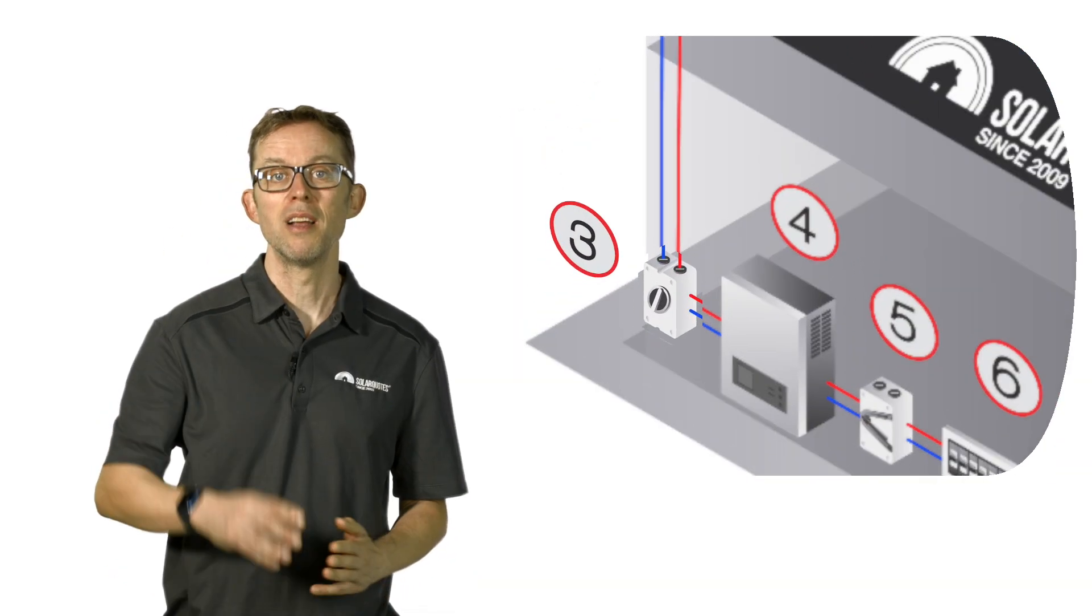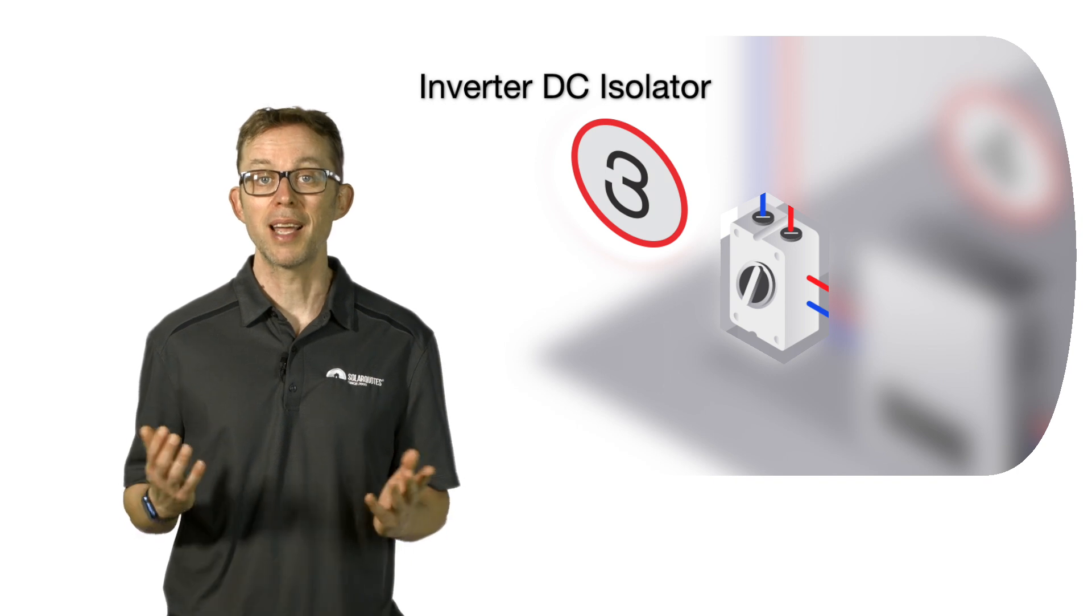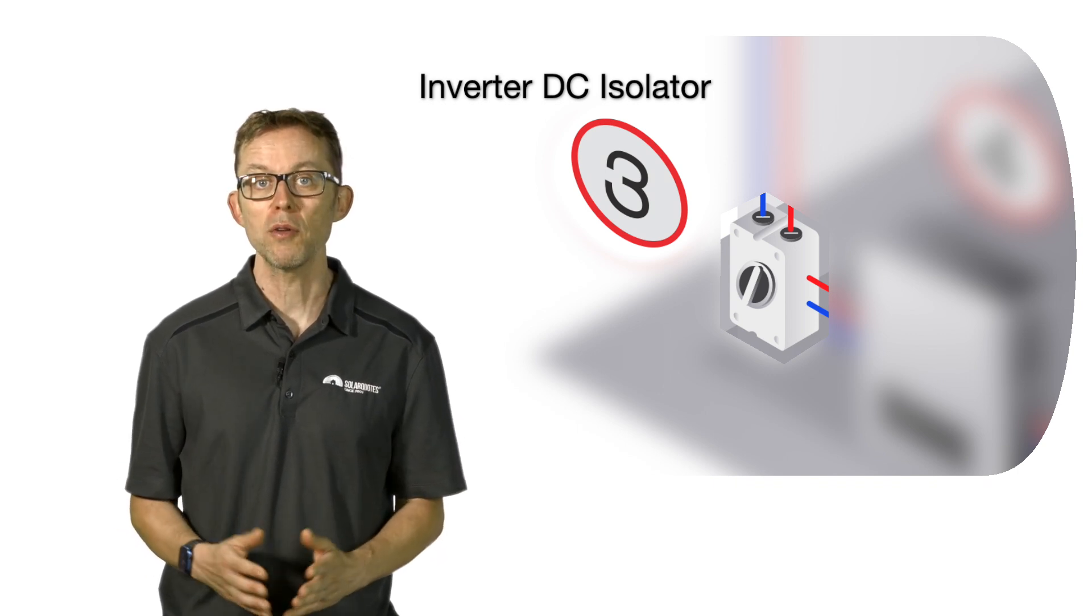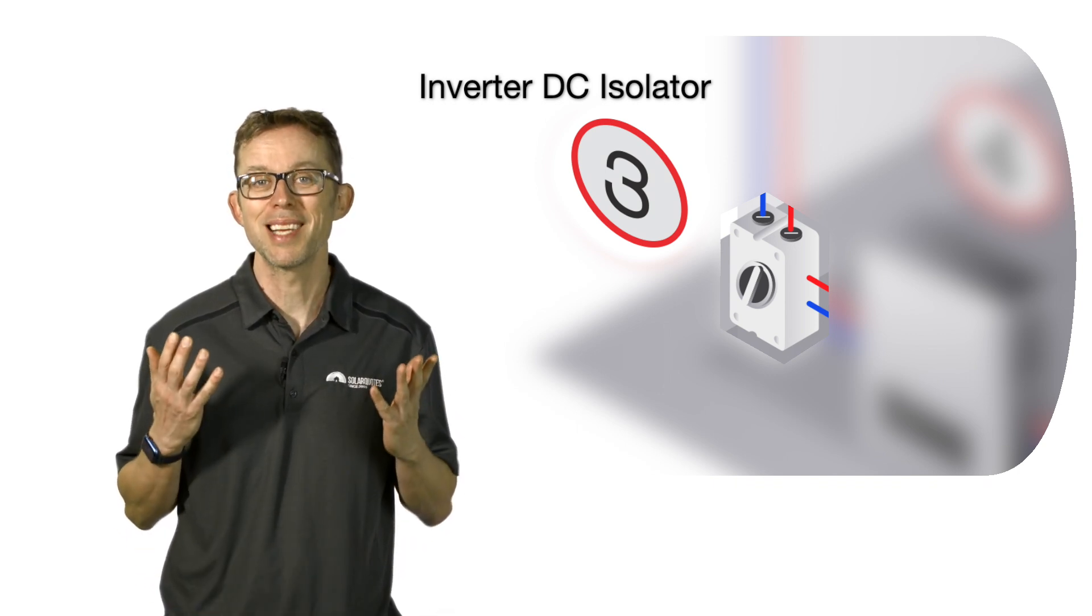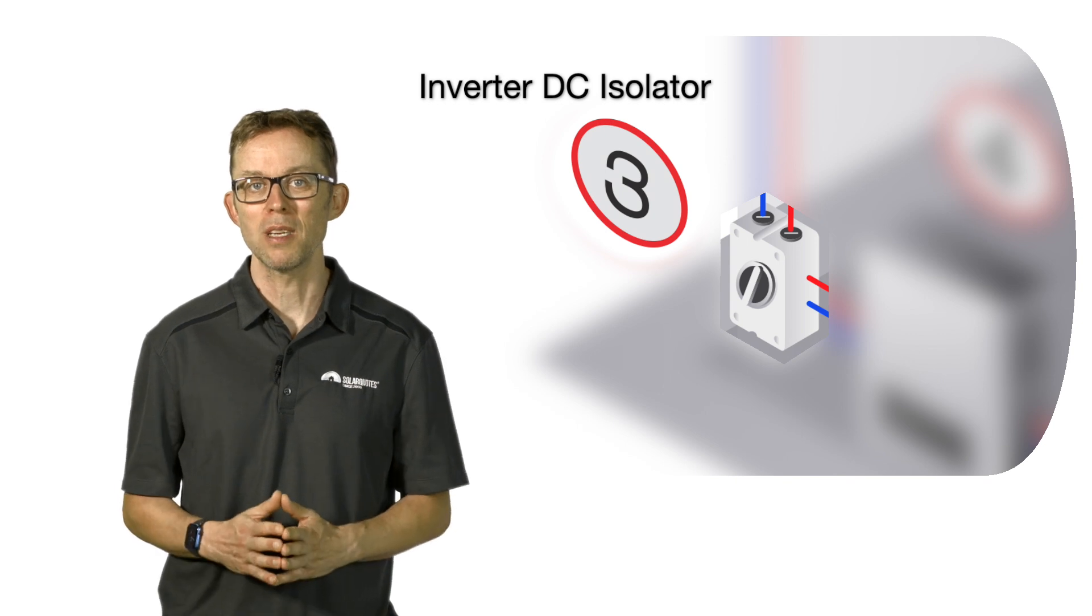Number three: the inverter DC isolator. Again, this is a switch that can disconnect the panels from the inverter, but it's at ground level next to the inverter. It's useful if an electrician needs to work on the inverter or de-energize the system for any other reason. Good modern inverters now come with a built-in DC isolator, which is a lot neater and presents less risk of bad connections or water ingress.